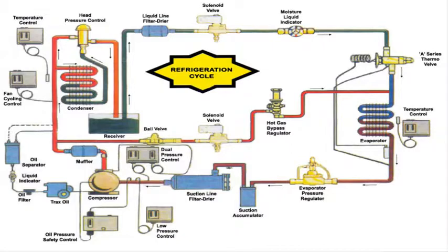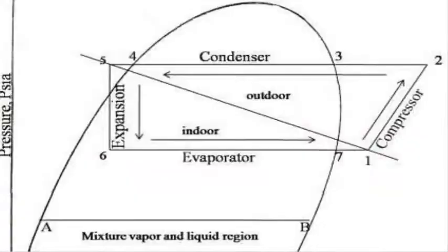After troubleshooting the refrigeration system, if there is enough air conditioner freon, or if the filter is dirty, we could know the entire thing by knowing the pressure and temperature of the evaporator, condenser, and compressor. Once we have found the pressure and temperature, we plot in the pH charts to determine where subcooling and superheat take place. Here is how P-H charts look.